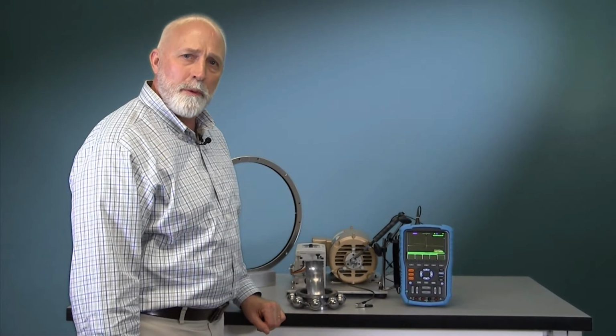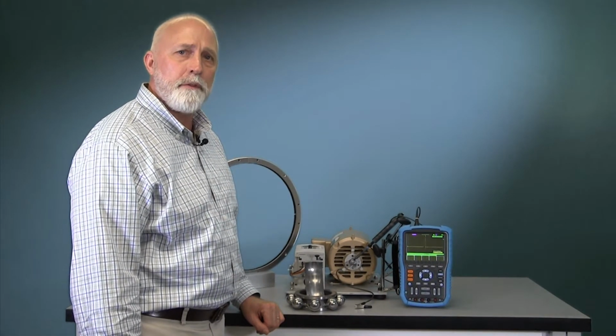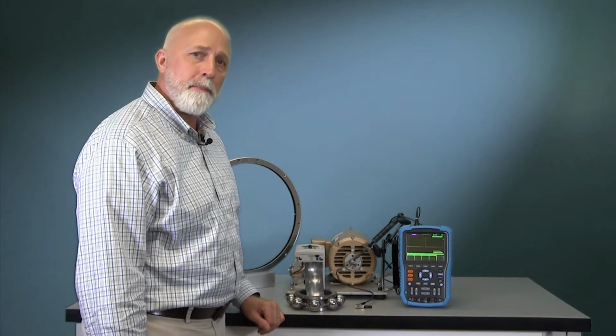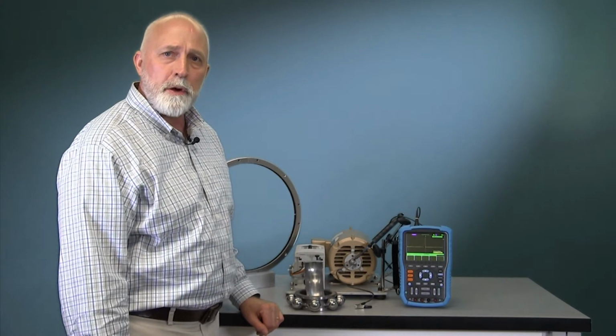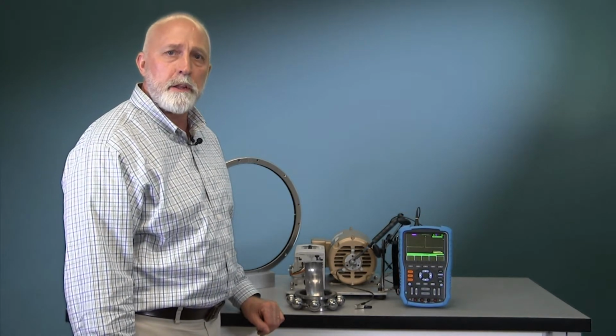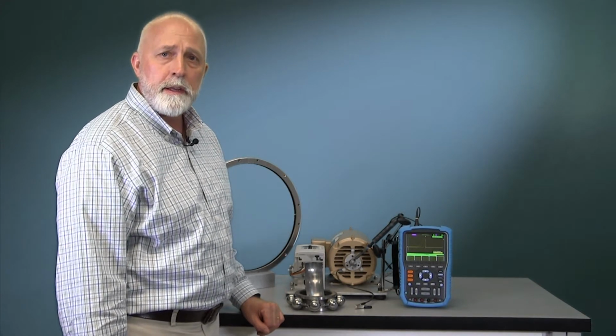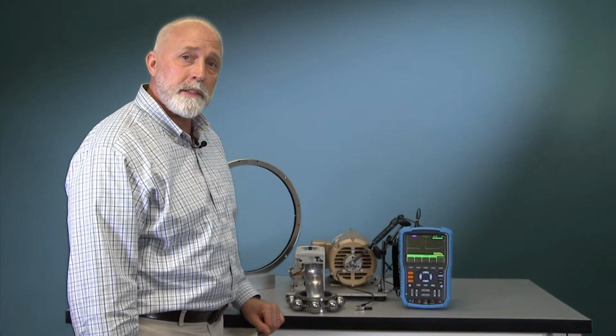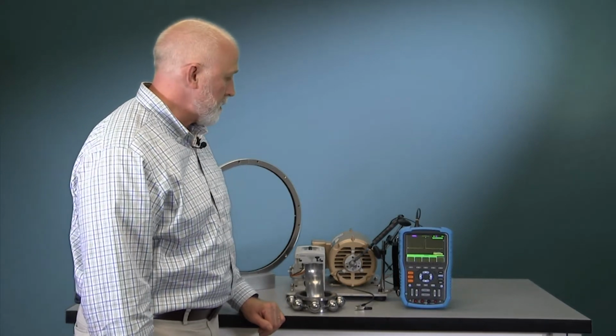Hello, my name's Adam Wilworth, and I'm here to explain shaft voltage testing on motors operated by a VFD. I'm going to show how the voltage is tested, and then we're going to look at the shaft grounding ring to see how to protect the motor bearings from destructive shaft voltages.